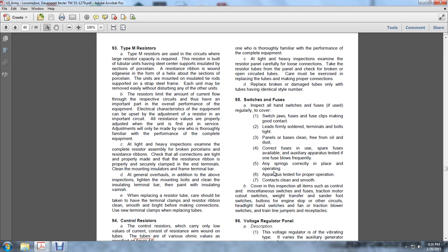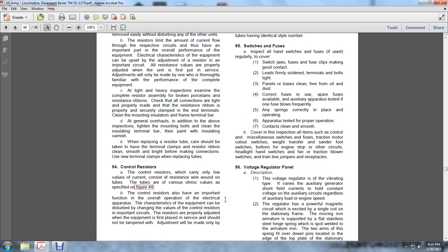When replacing a resistor tube, care should be taken to keep the terminal clamps of the resistor ribbon clean, smooth, and bright before making connections Use new terminal clamps when replacing tubes. 94, control resistor. The control resistor, which carries only low values of current, consists of a resistance wire wound on a tube. The tubes are of various ohmic values as specified in figure 44.